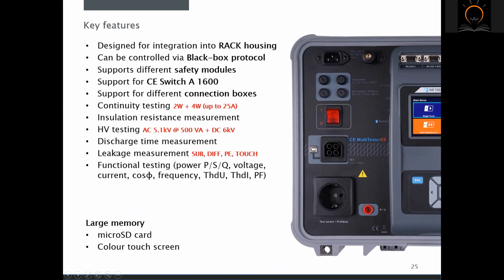All of the key features of our solution have already been shown in the previous slides, but in order to sum them up, they are listed here once again. For the integration of the test instrument into the test system, Metrel has designed rack adapters and rack housings. Using the black box protocol, it is possible to control the test system via external software applications such as Visual Basic, C++, and LabVIEW.